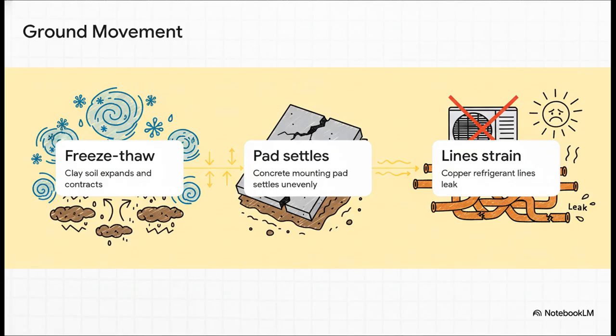Step 1: those winter freeze-thaw cycles cause the clay soil around your house to expand and contract. Step 2: the heavy concrete mounting pad that your outdoor unit sits on begins to settle unevenly because of that shifting earth. Step 3: the copper refrigerant lines attached to that unit are rigidly fixed to your house, so as the pad sinks, those copper lines are pulled and strained until they eventually snap or leak. Literally, a single millimeter of shifting clay in November can lead to a complete loss of your home's cooling capacity on a 90-degree day in July.